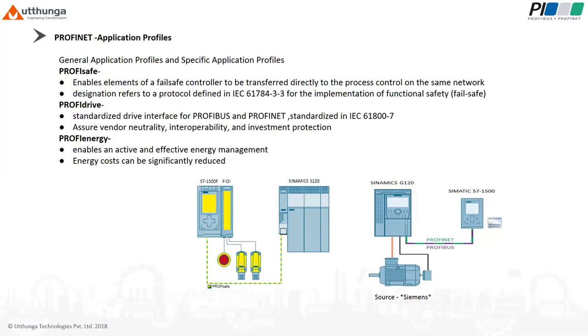PROFIDRIVE refers to the specification of a standardized drive interface for Profibus and PROFINET. This application-oriented profile, which is standardized in IEC 61800-7, contains standard definitions for communication between drives and automation systems. Thus, it assures vendor neutrality, interoperability, and investment protection. In the right side image, you can see it will be protecting the drives, whether motors or VFDs.